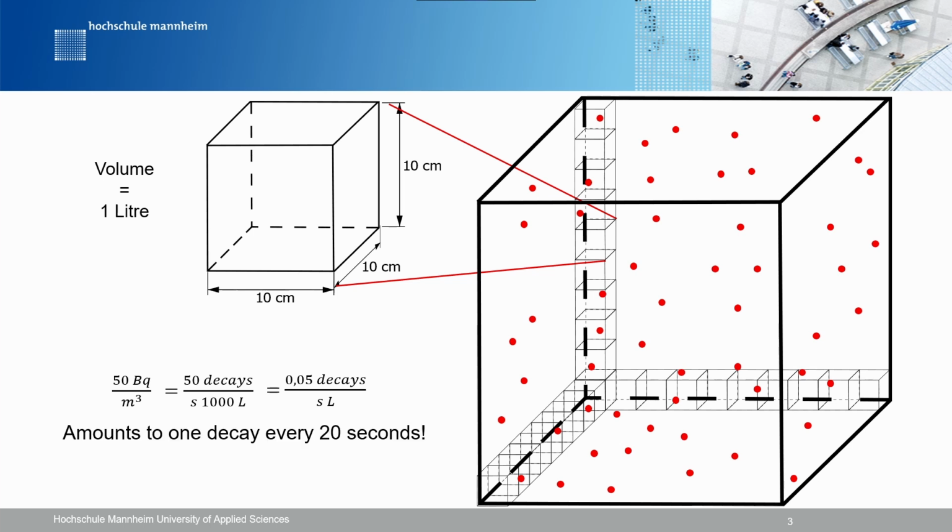If we assume a more realistic counting efficiency of 5%, we would record 0.0025 counts per second. If you remember that the background is fluctuating between 0 and 1 pulse per second, it becomes apparent that this value is indistinguishable from the background, even with extended measurement times. In this example, it does not matter so much in which position the front lever is placed.